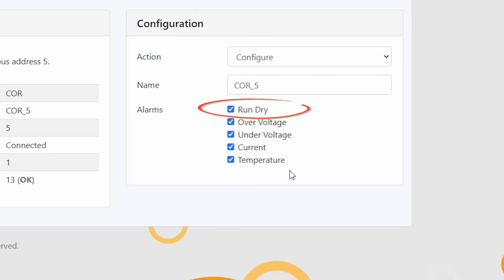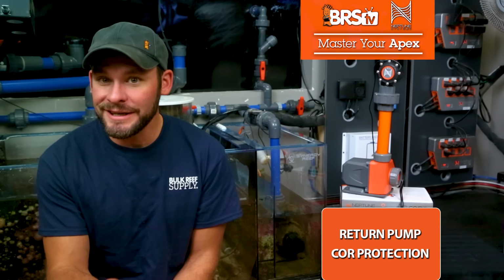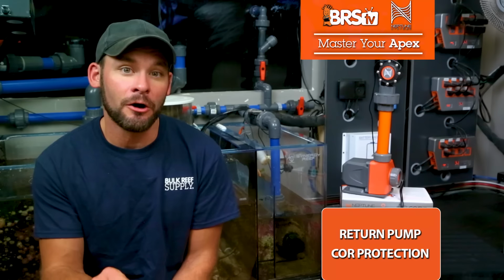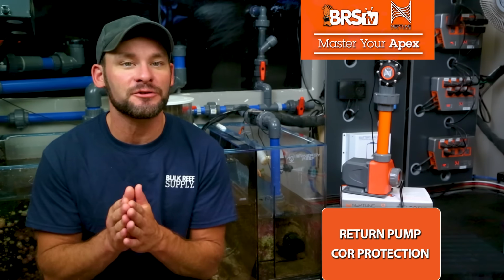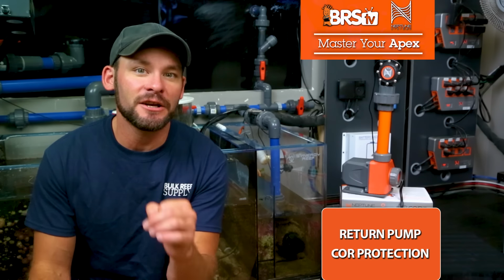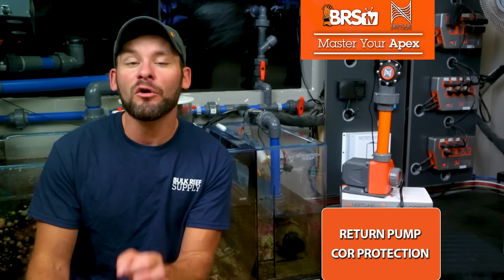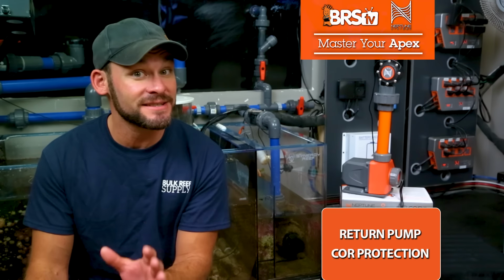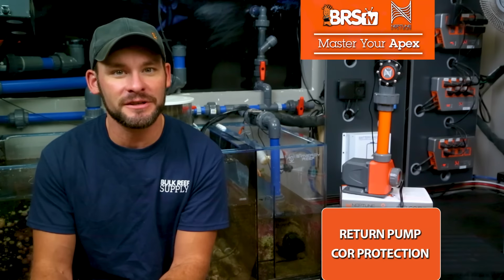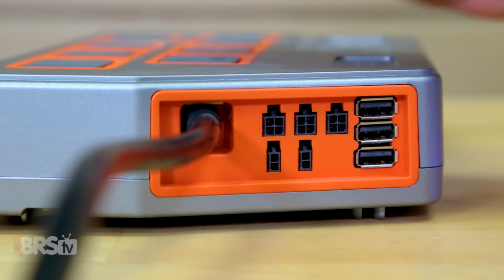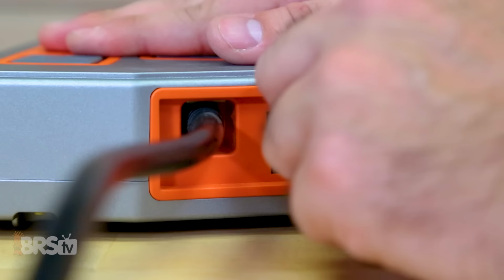and power monitoring. What that means is instead of only being able to use power monitoring alone for a diagnosis tool for a potential issue, using the COR 15 and COR 20, you gain access to more intelligent troubleshooting, oftentimes well before the pump actually breaks, and accessing them is automatic just by hooking your COR pump to your Apex and running the COR task function.